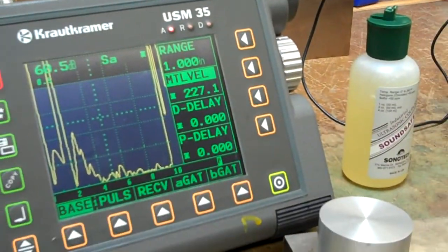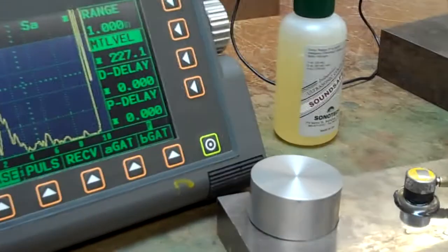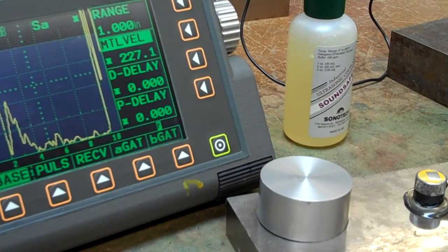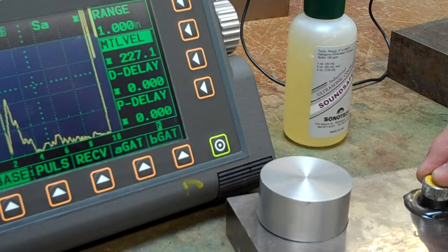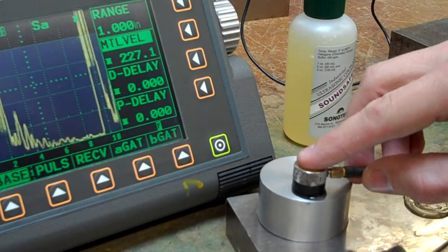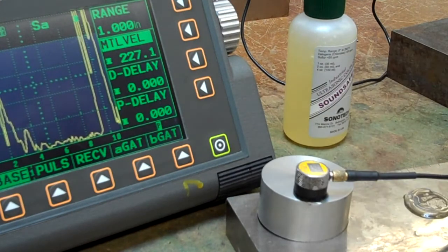Back up so you can see the transducer on the piece of steel - coming up at 100%. Now on our piece of aluminum, 1-inch thick, it comes up at about 94%. So that tells us the velocity is a little faster in the aluminum.